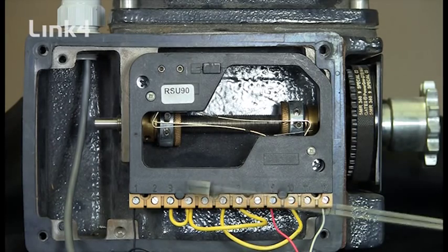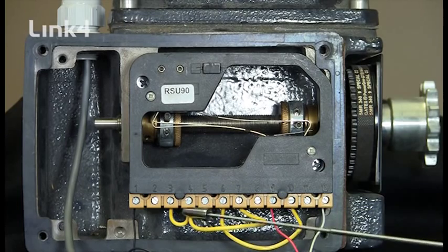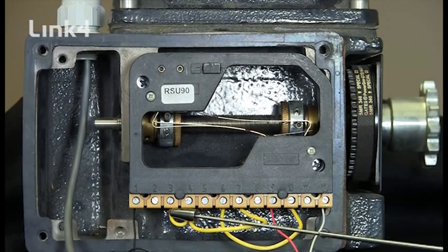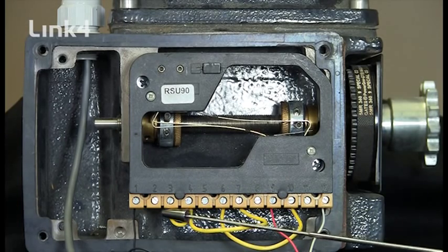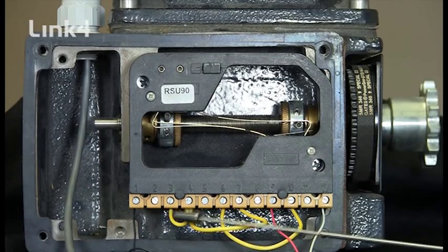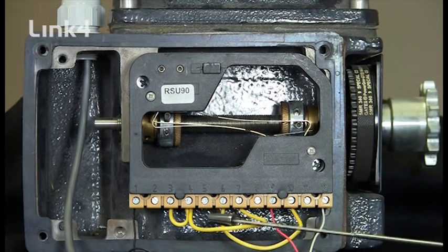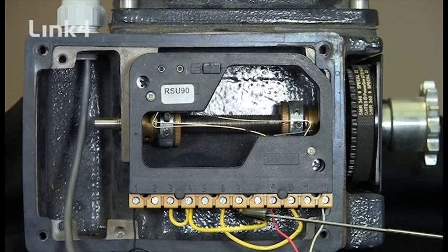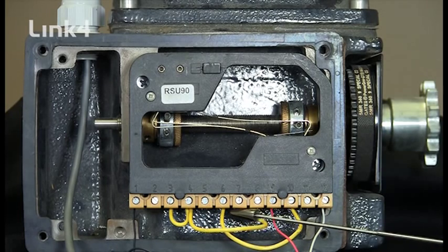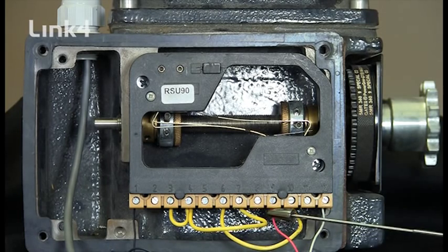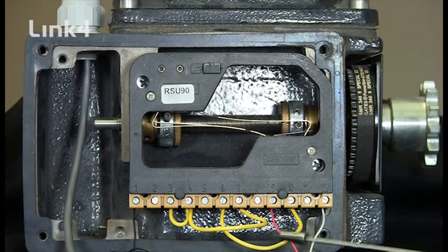We then take our 24 volts and apply it to number 3 which is the direction 1 limit in this particular case for our open. And then we come over and we also jumper it to number 7 which is direction number 2's limit in our particular instance close.